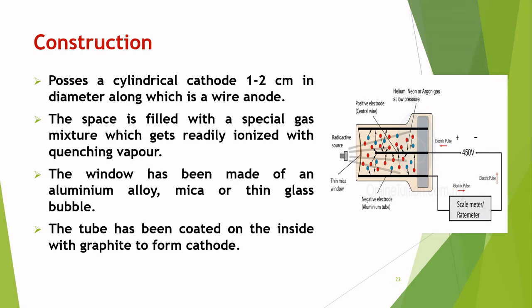Construction of Geiger-Müller counter. A Geiger-Müller counter possesses a cylindrical cathode which is usually 1 to 2 cm in diameter, along the center of which is a wire anode. The space is filled with a special gas mixture which gets readily ionized, together with a small proportion of a quenching vapor. Quenching vapors are used in the Geiger-Müller counter for performing several functions, such as to prevent the spurious pulses that may get produced due to the positive ions reaching the cathode, and to absorb the photons emitted by the excited atoms and molecules returning to their ground state. Both chlorine and bromine are generally employed as quenching agents.